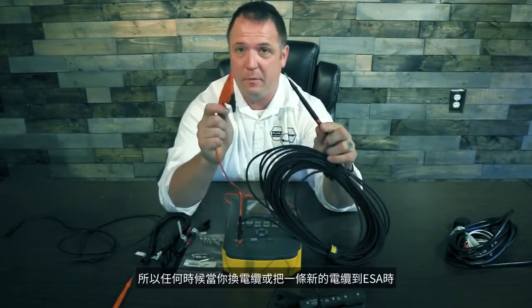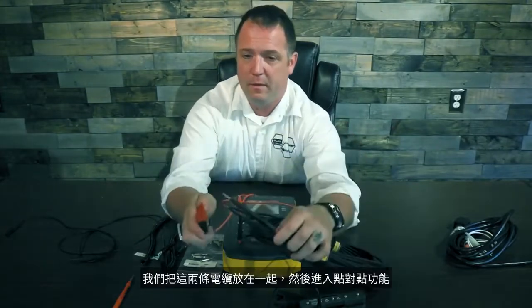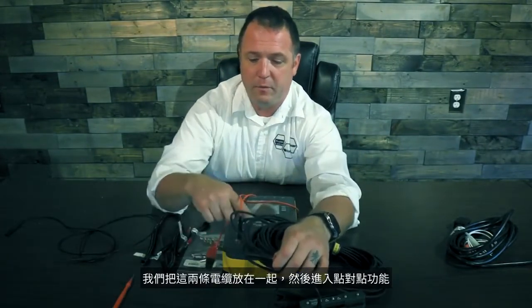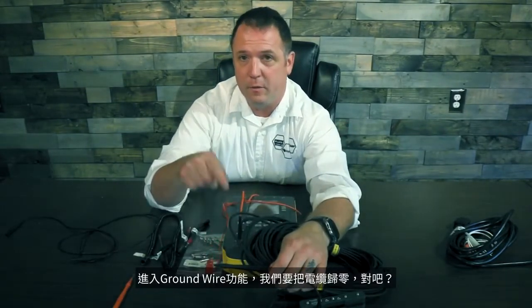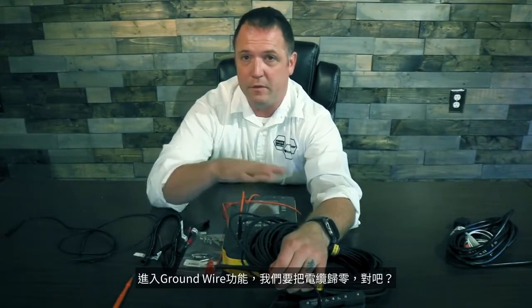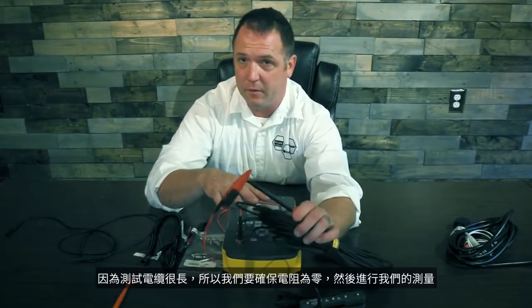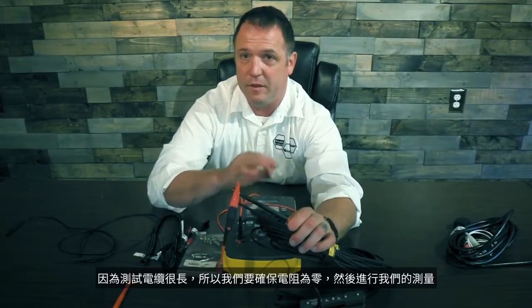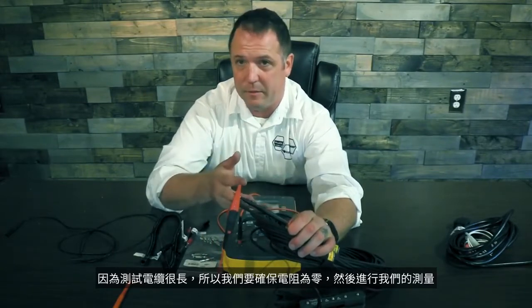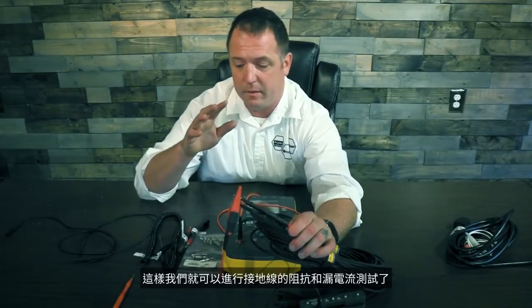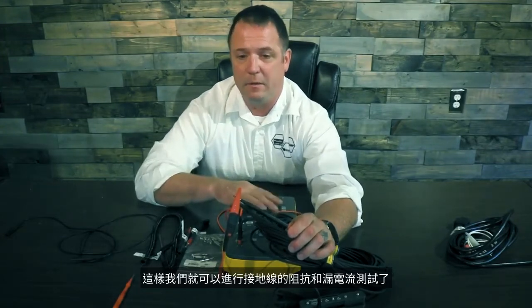So anytime you change cable or introduce a new cable to the ESA, we want to put the 2 together. We go into the point-to-point function, go to the ground wire function, and we're going to zero the cables out, right? Because there's a lot of length here, so we'll make sure that resistance is 0, then take our measurements. So we can do our ground wire resistance and our leakages.